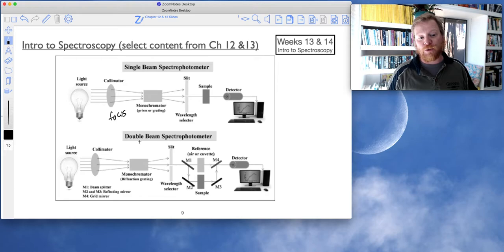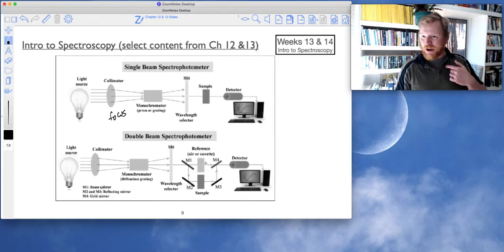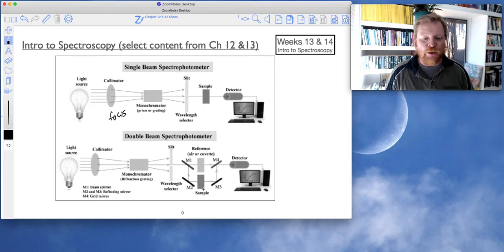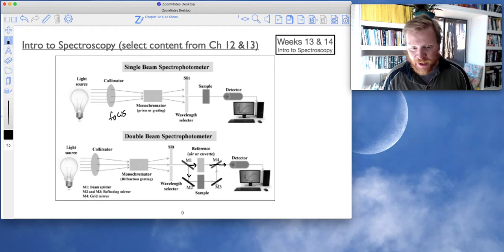So the really fancy spectrometers are double beam instruments where you will load in your reference, and this says air or cuvette, cuvette containing the solvent is what I recommend, and then your sample. And again, we hope that this reference or this background is as identical as possible to the sample. And so now this is pretty cool. So the setup is almost identical to the single beam, except for now we have here, you can see M1 is a beam splitter. So half the light will go down this way, and half will go down this way. So the half that goes through the reference will just pass right through what's called this grid mirror, and this grid mirror allows light to pass through from one side, so it's transparent on one side, and it's opaque on the other side.